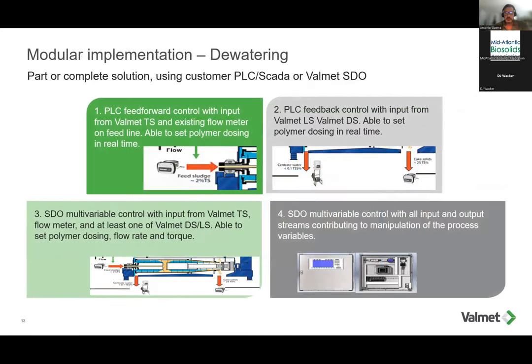It is a scalable type of application. Meaning what I just showed you, the complete package, takes into account all those measurements, or the more measurements you have, the more you know what's happening in your input and output streams, the more you can control it in an efficient manner. But typically, an easy way to start is to just use a density meter on the inlet stream. With that into your PLC system, you can start optimizing polymer dosing in real time because you do know what's coming into the system. So that's the simplest way to do things.